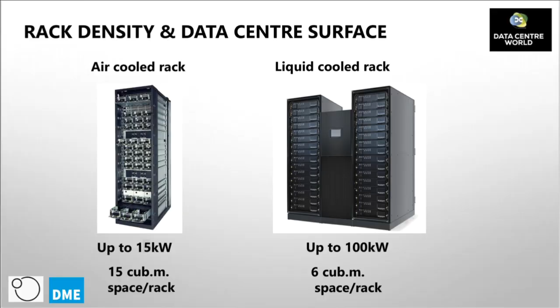Comparing the space needed for those two different models: the traditional one needs 15 cubic meters, because you need space in front for the cool aisle and at the back for the hot aisle, plus underneath for the raised floor and above for the ceiling. All in all, 15 cubic meters, so three times more, but the density is 7 times more with the liquid cooling in comparison to the traditional air-cooled one.